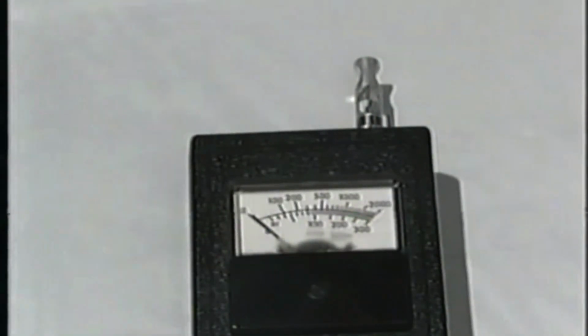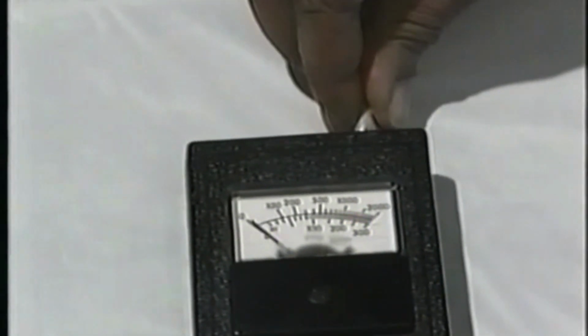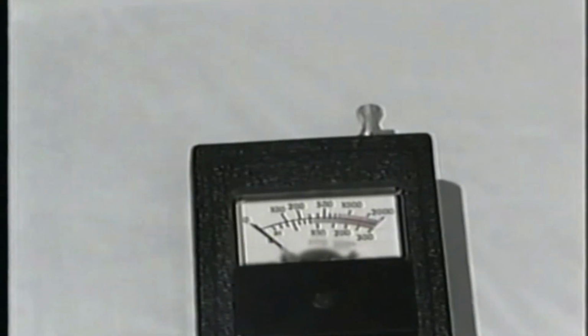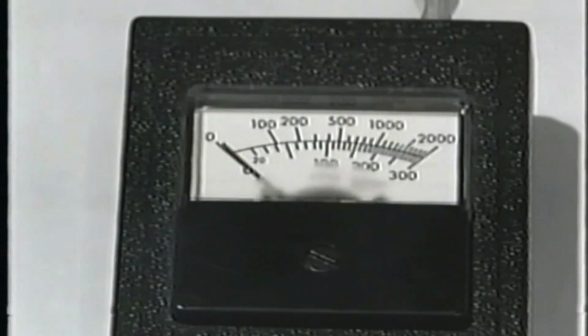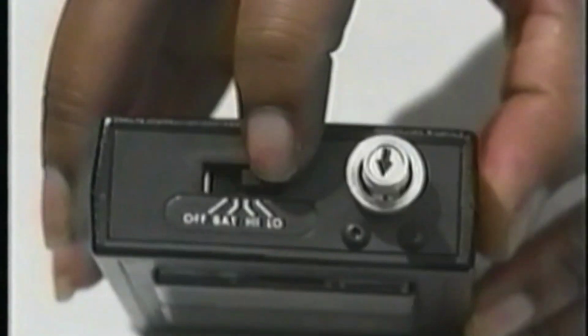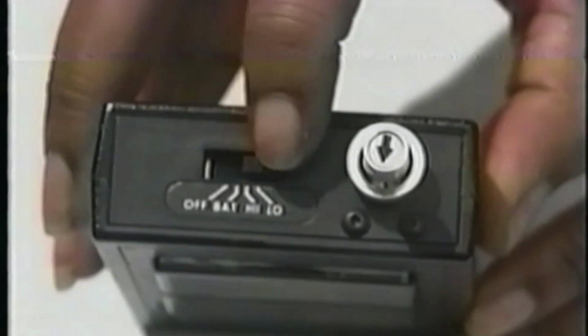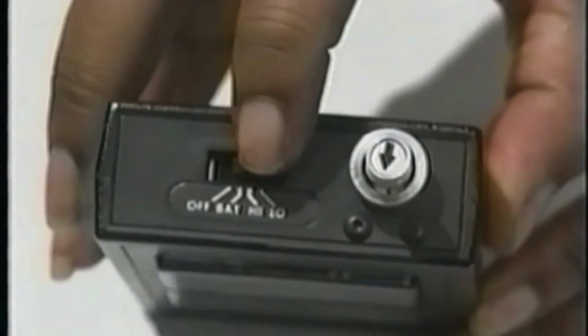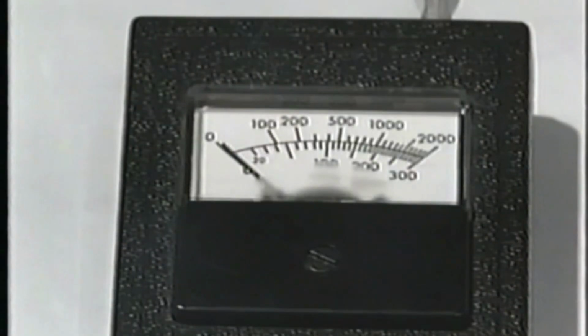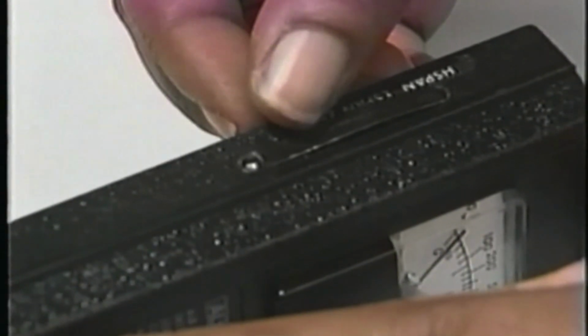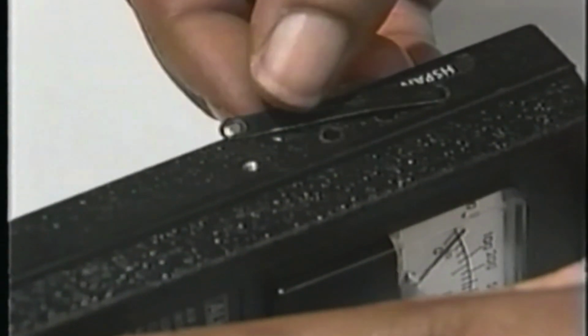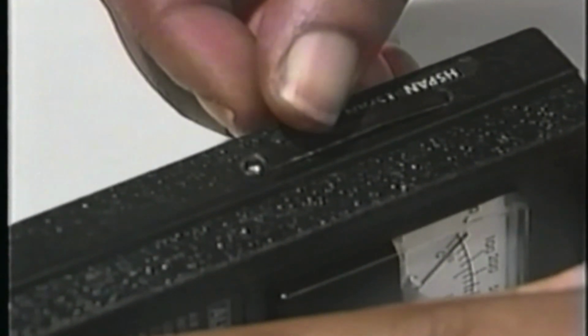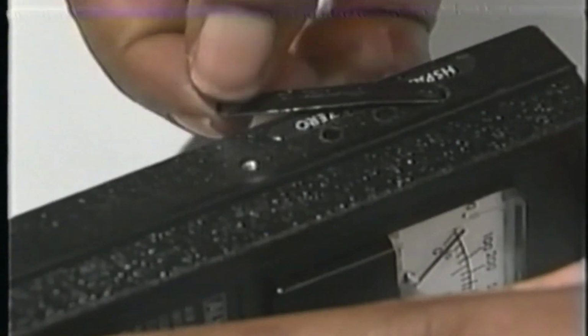As a final check and adjustment, be sure that the probe has been retracted into the case to prevent any airflow from passing the sensors, and check so that the meter reads 0 when the switch is set to either the low or high position. If it does not, repeat the 0 and span adjustments as required until all 3 meter readings are correct without additional movement of the screws. Then replace cover. To verify calibration, you should check the meter against 2 additional velocities on each scale.